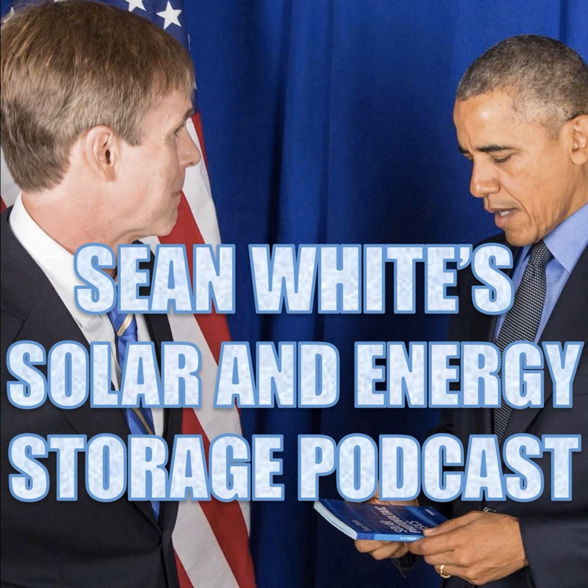There are many factors to deal with here, and grounding electrode systems outside of PV are also hard to understand because the way they are implemented differs regionally. Factors such as wet earth, dry earth, lightning vortexes, corrosion, living on a rock, stray currents, proximity to large power production systems, and more will influence people's opinions on how to properly connect to earth. Refresher: EGC equals equipment grounding conductor, GEC equals grounding electrode conductor.